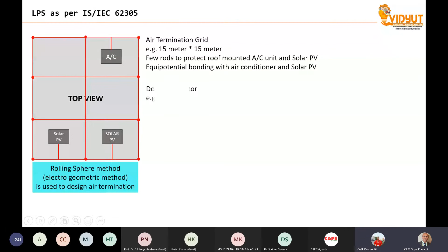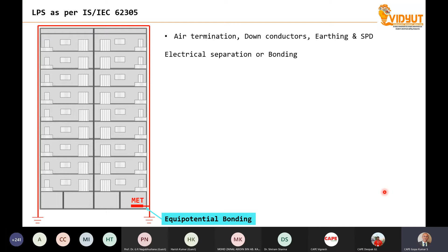So now the second part, as I said, is the down conductor. A number of down conductors are required because the total lightning current shall be divided through different paths in order to reduce the effect of the lightning current. Then at the building, we need to have equipotential bonding. That means the down conductor and the electrical installation bus bars, the earth bus bar, shall be interconnected. The power lines and data lines, the service lines coming into the building, shall also have surge protective devices. Every down conductor should have an earth electrode. The calculations for how to design the earth electrode are given in the standard. In modern buildings, the easiest way is to make a foundation earthing, meaning the structural steel and the steel reinforcement inside the building can be used as the earth electrode. So this is how the lightning protection system is designed according to IEC 62305.